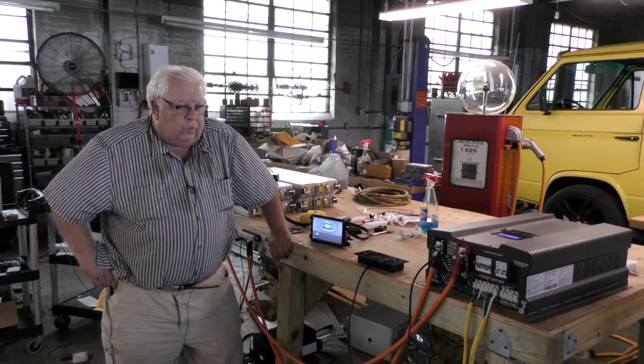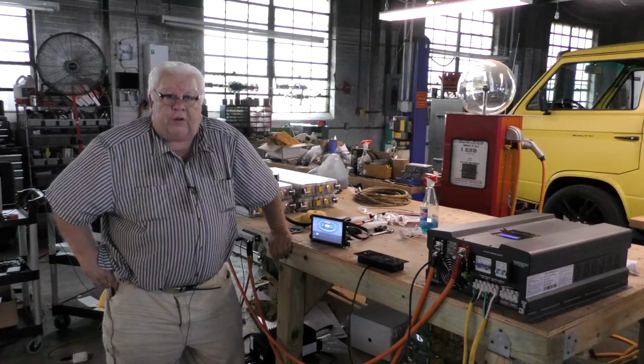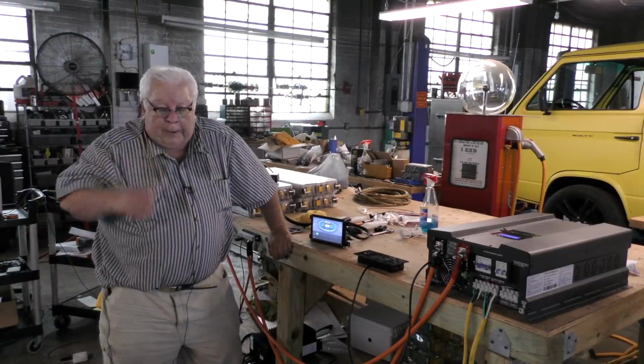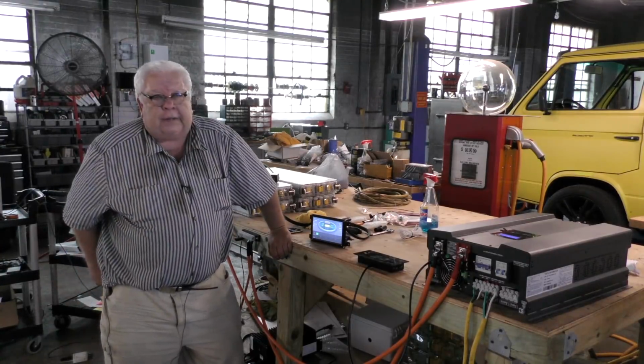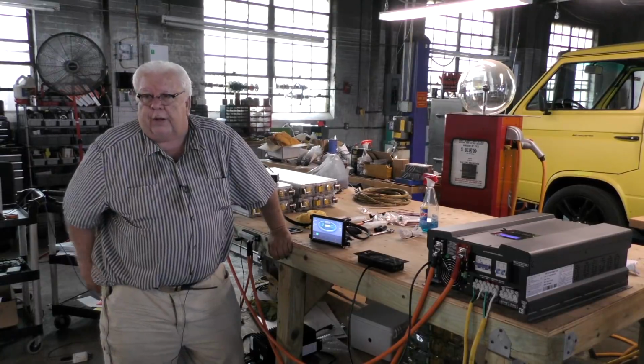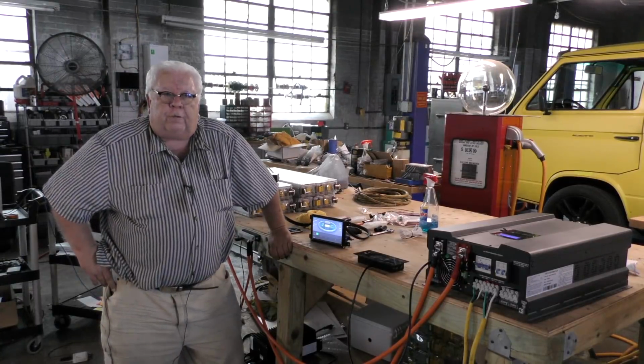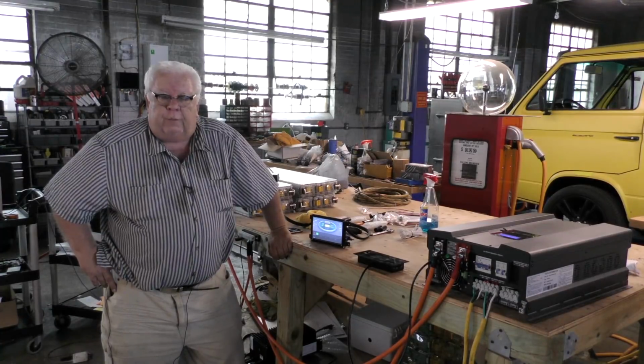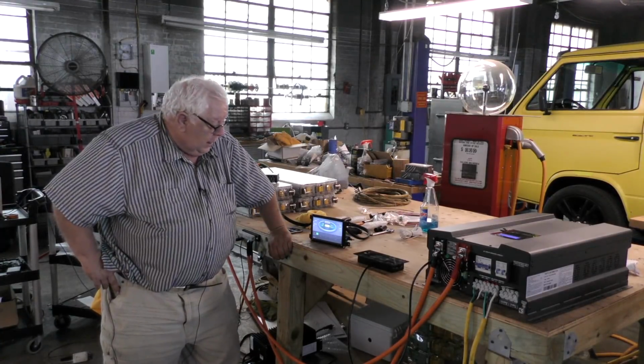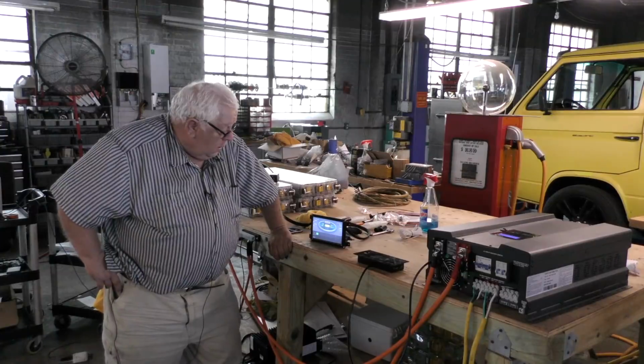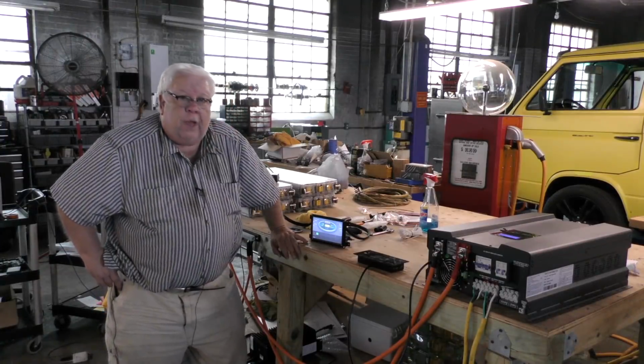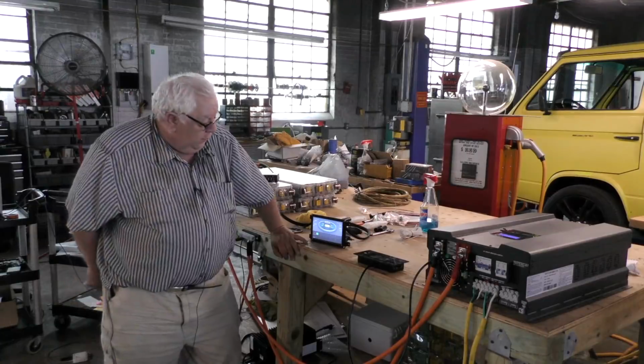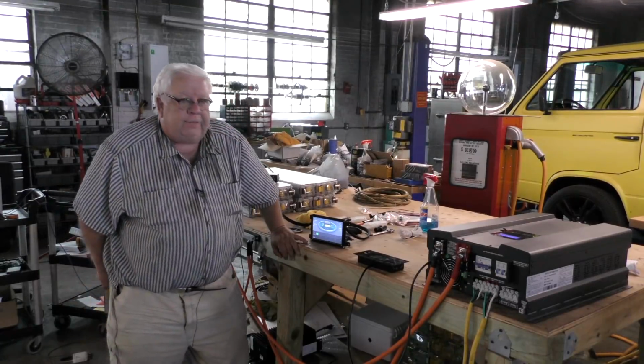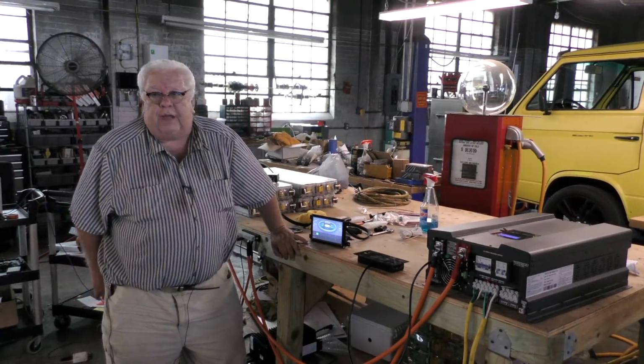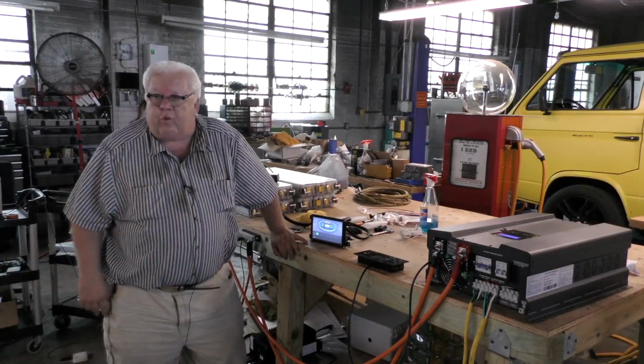So one of the things we're going to do is take our charge enable output of our battery controller and use it to control a contactor connecting the grid-tied inverters to the system, much as we did with the MPPT charge controllers, and kind of for the same reasons. And so right now, even with two of them up, we're using 44 amps out of the system because of the overcast haze. Let's go turn on number 3 and see what effect that has.